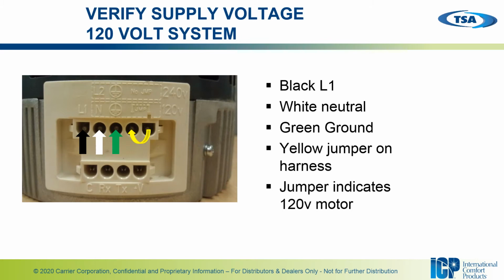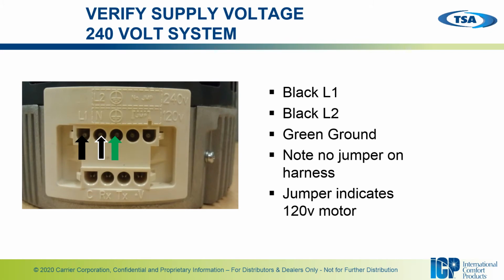So checking for your high voltage, simply check between the black wire and the white wire. Okay, if for some reason you don't have voltage there, check between line 1 and ground and make sure that you do not have a broken neutral. And of course, on a 240 volt motor, you're going to check between line 1 and line 2, and you should have 240 volts or maybe even 208 volts if you're in a commercial application. All right, but another thing to point out is that we have no yellow jumper between the 4th and 5th pin on this harness.